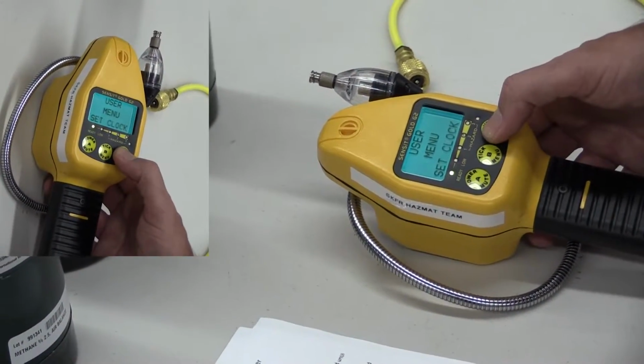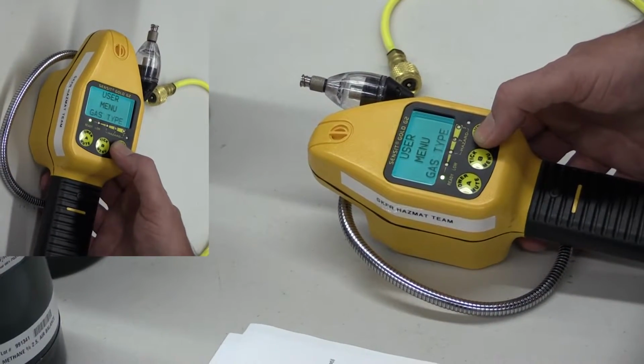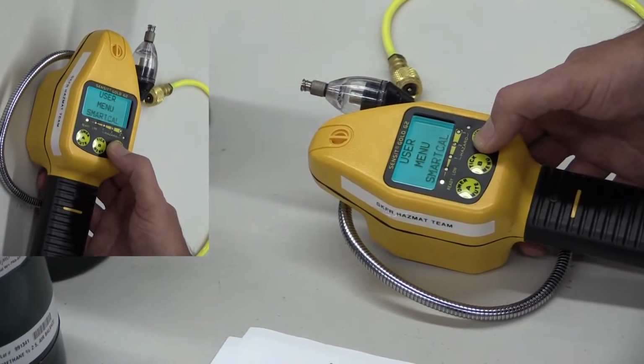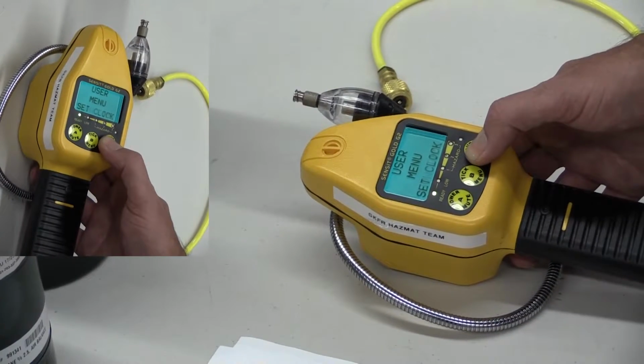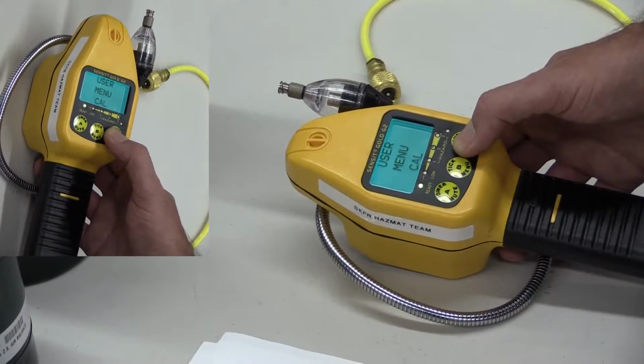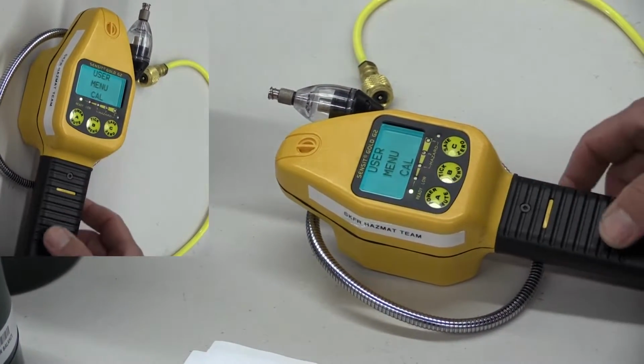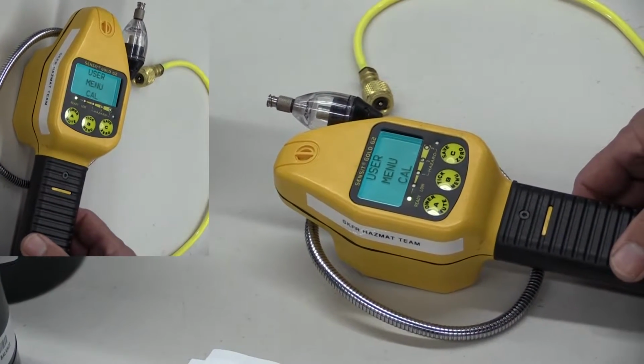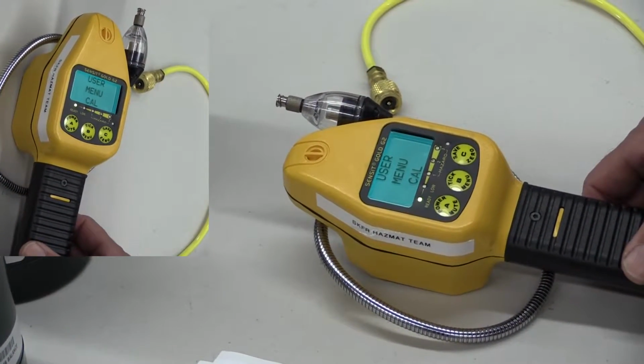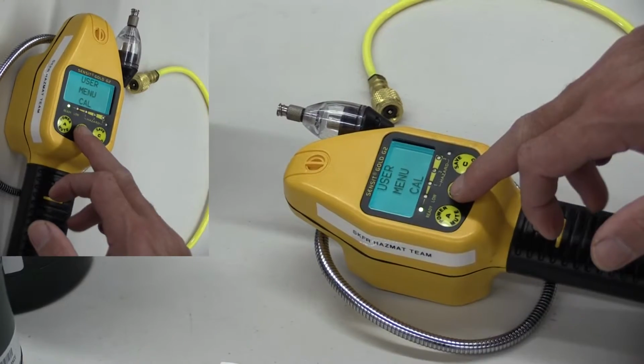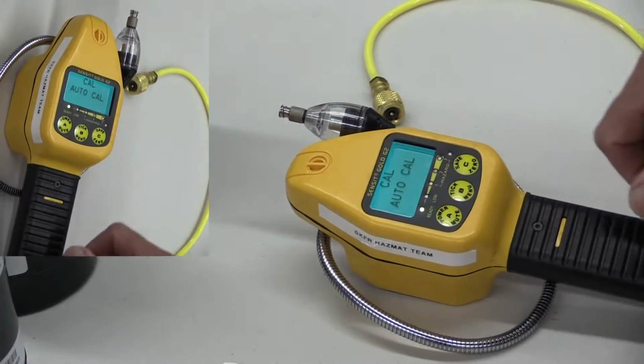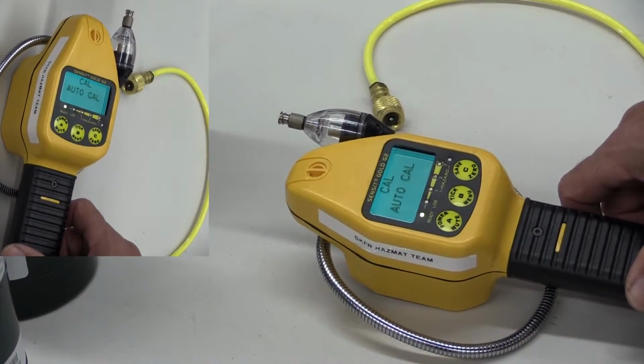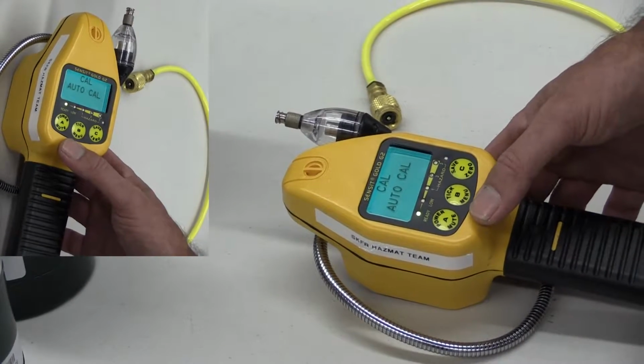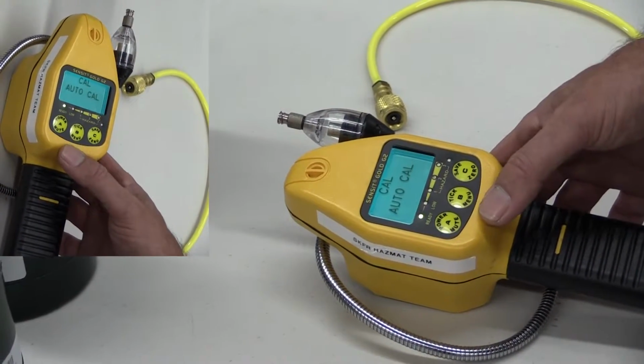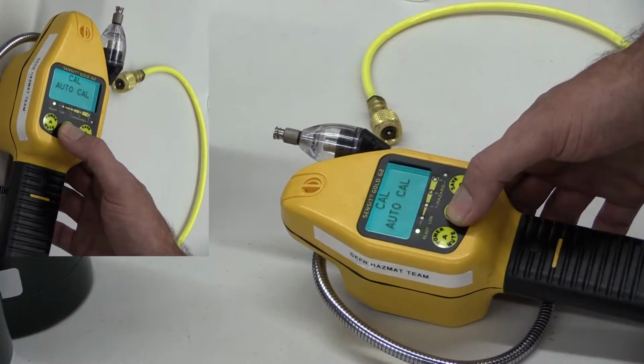We'll walk through the user menu until we get to calibration. We're going to press the B button and the words Auto Cal will show on the screen. This says we're ready to start the calibration. So to start the calibration, we're going to press the B button from this screen.